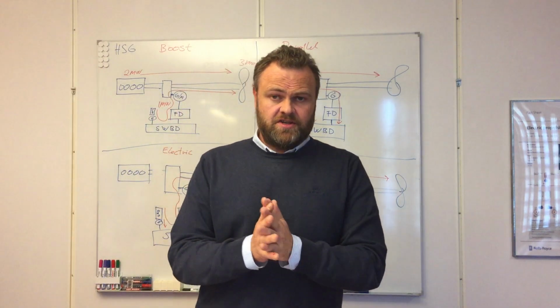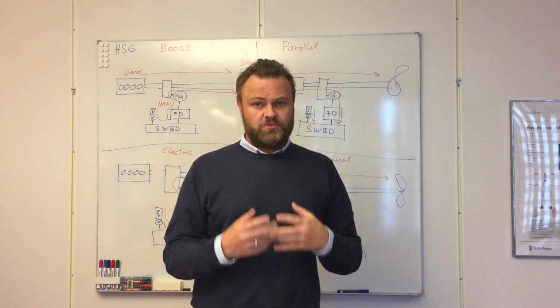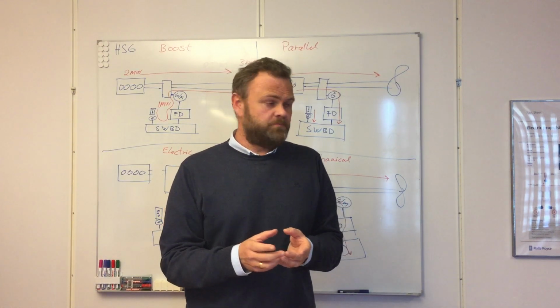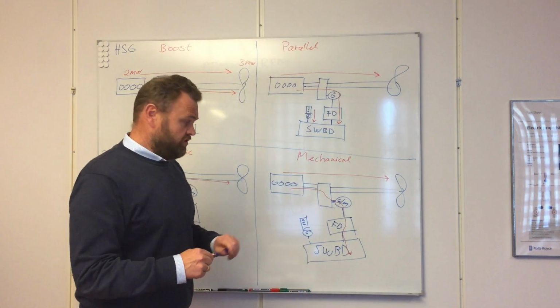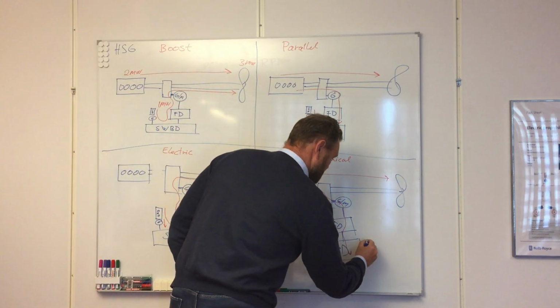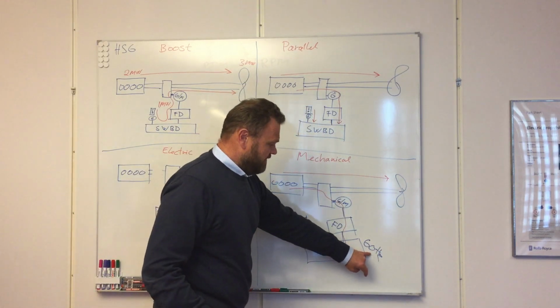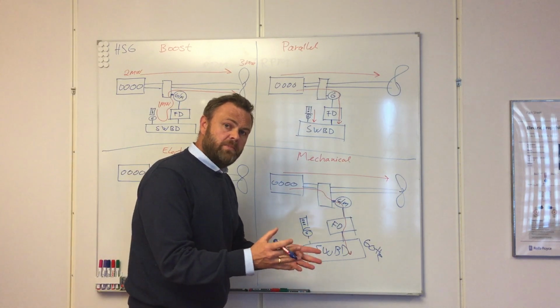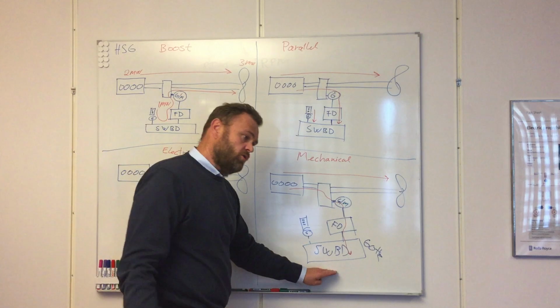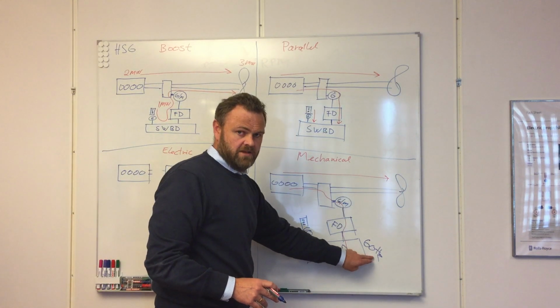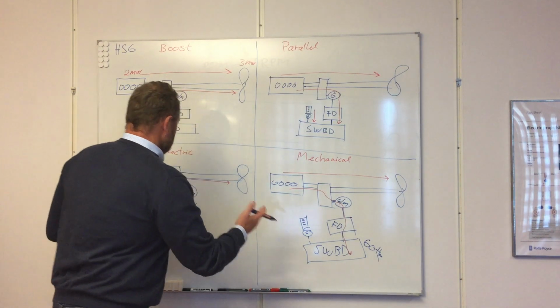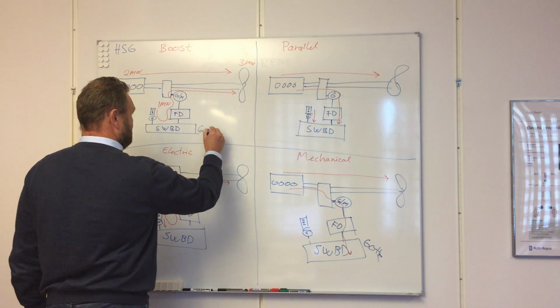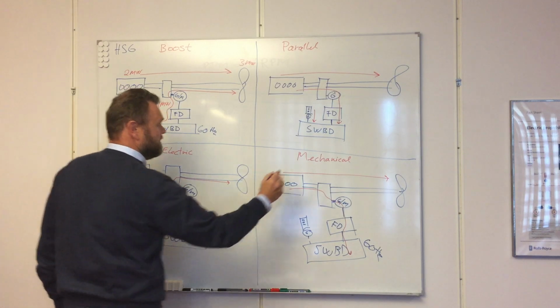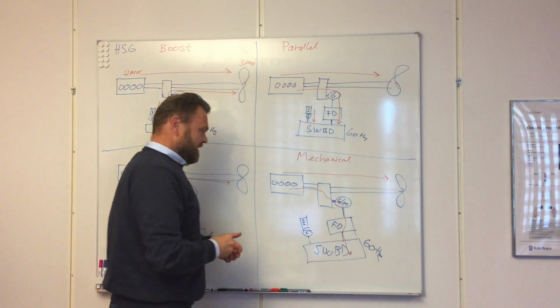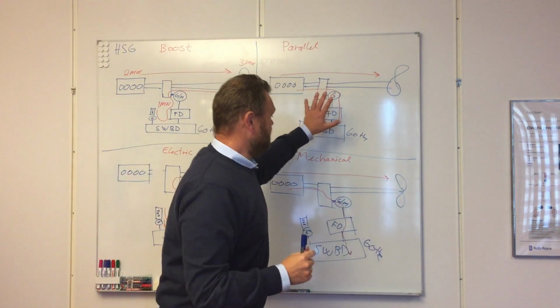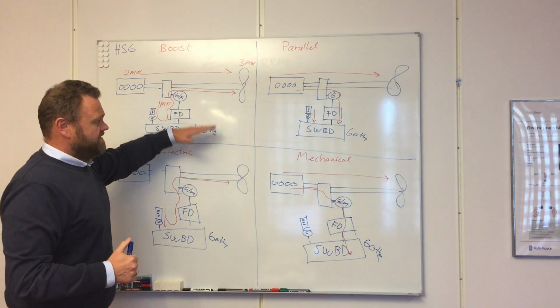Back to one of the other sessions, you have heard me say that the switchboard needs a fixed frequency. On board a vessel you will have typically 60 Hertz, and you need that frequency of the voltage to be stable for all the equipment connected to the electric network on the complete vessel. So in all these situations, the voltage frequency in all different operational modes always has to be 60 Hertz stable.